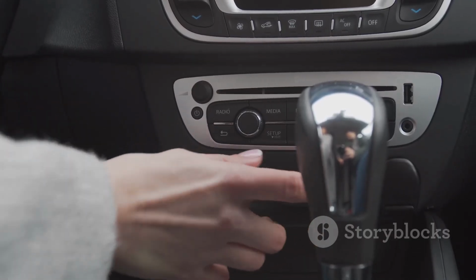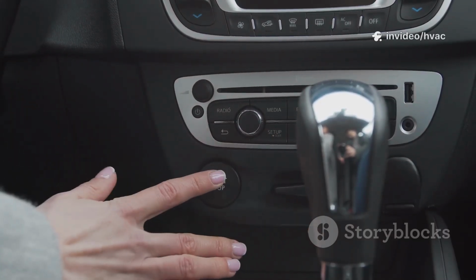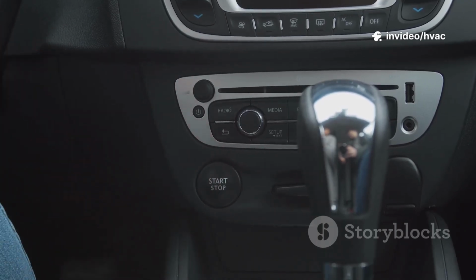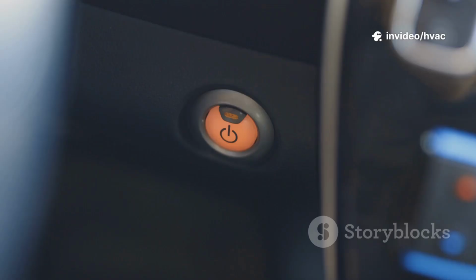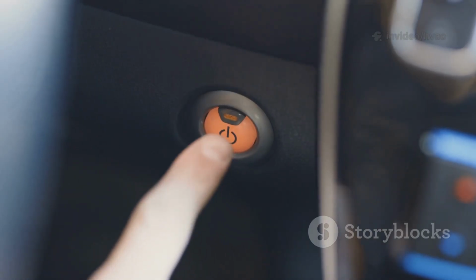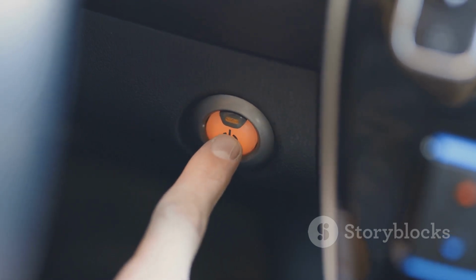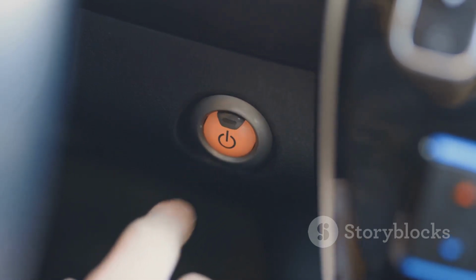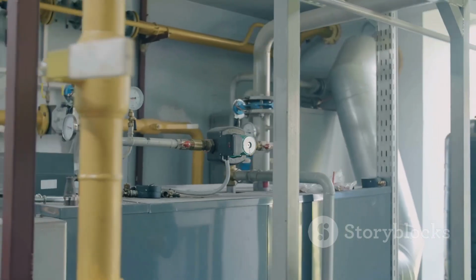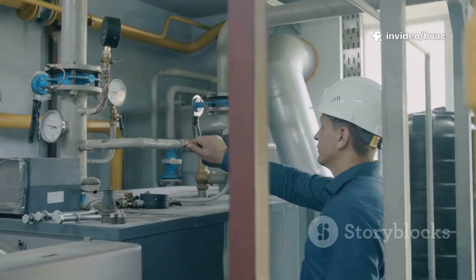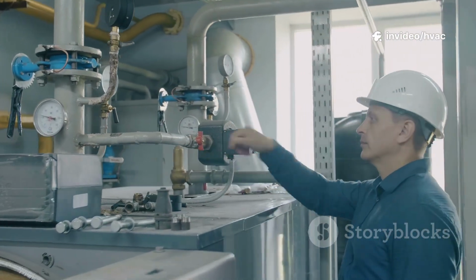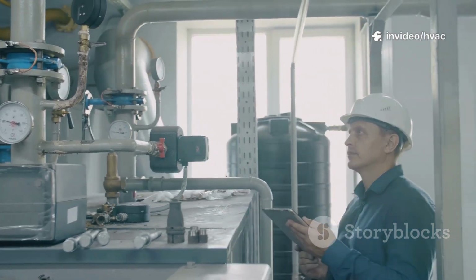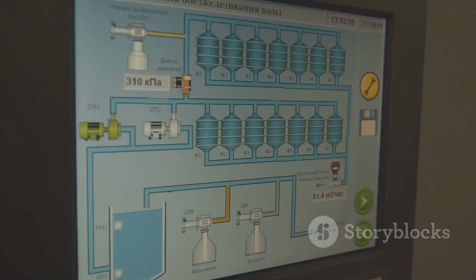Imagine your car's ignition. The interlock only lets you start the engine if the gear is in park. Here, a NO contact is used. When the gear is in park, the contact closes, allowing the starter circuit to energize. If it's not in park, the circuit stays open, no start. In HVAC, a chiller won't start unless the water pumps are running. Here, the pump's auxiliary contact is wired as NO. When the pump runs, the contact closes, sending a go signal to the chiller. If the pump stops, the contact opens and the chiller can't start, protecting the equipment.